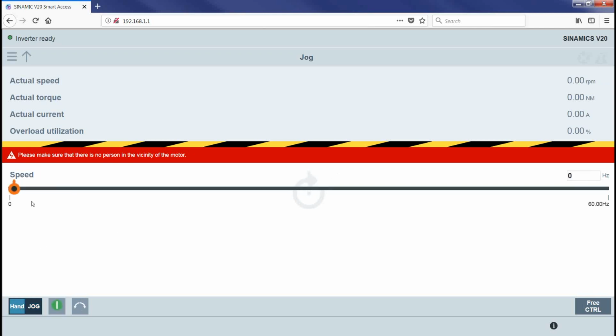Hand mode I'll select. So here we've got the speed slider. So we pick the speed we want to run. I'm going to just go 30 hertz. And hit start. And at the top of the screen here, you can see actual speed in RPMs. So 900, half of 1800. Actual torque, actual current to the motor, and overload utilization where we are right now. So that's the jog mode. Stop. So we also have to make sure we free control to give up control from this jog screen. It's going to make sure it's good. A little safety warning.